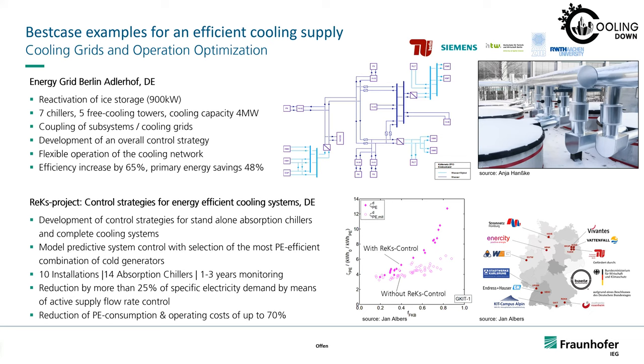A model predictive system control was used in order to minimize the energy used, also in terms of primary energy, so that the cooling generation becomes efficient. The reduction achieved here is at the level of 25% for specific electricity demand, and the primary energy consumption and operating costs can be reduced up to 70%.